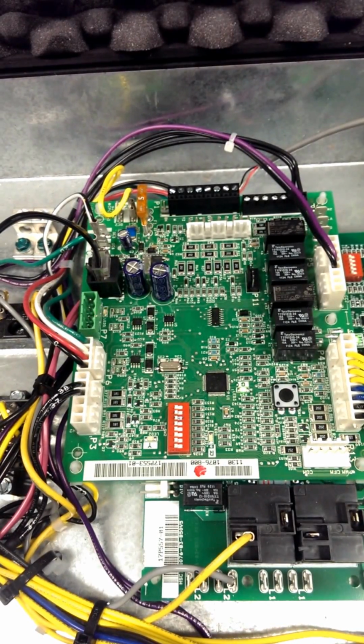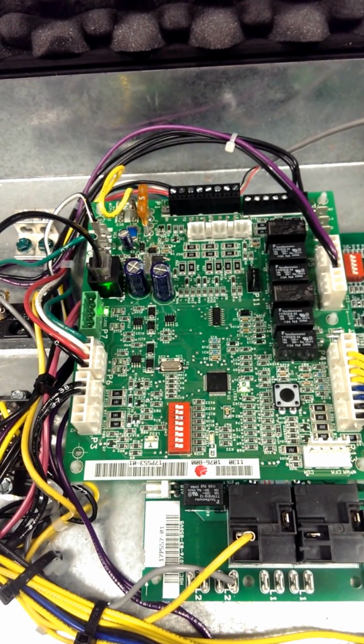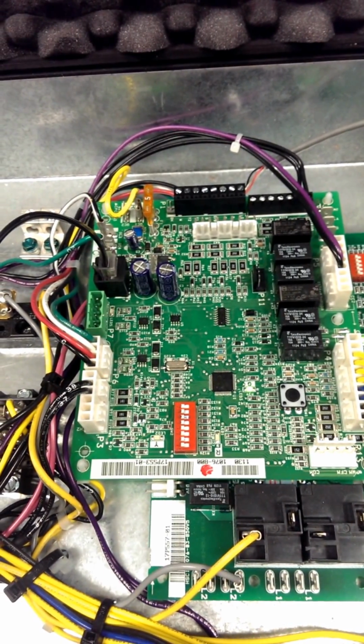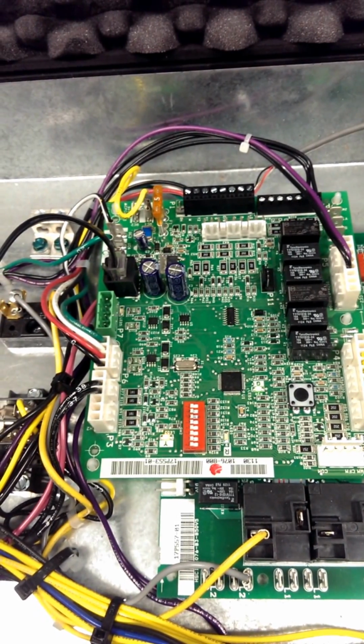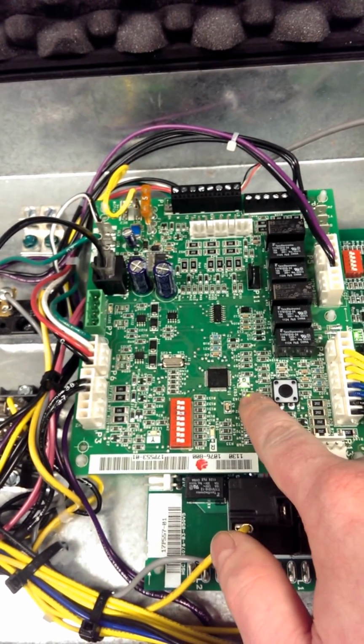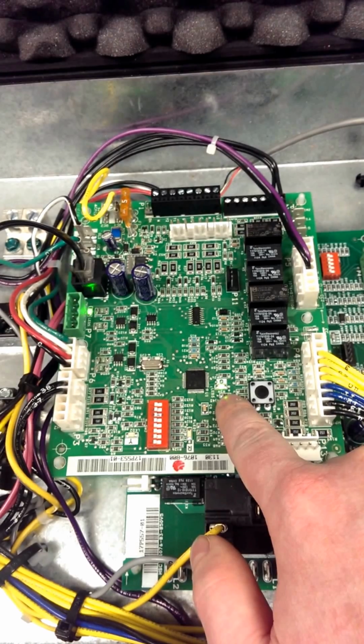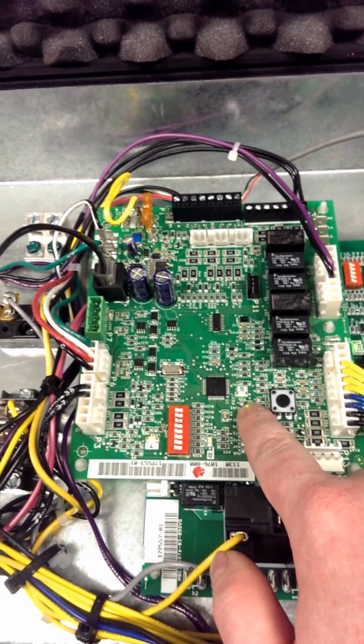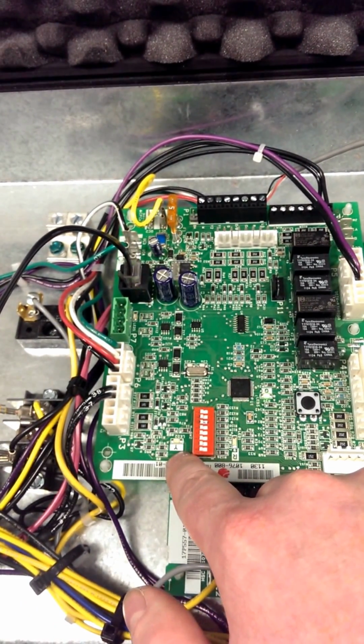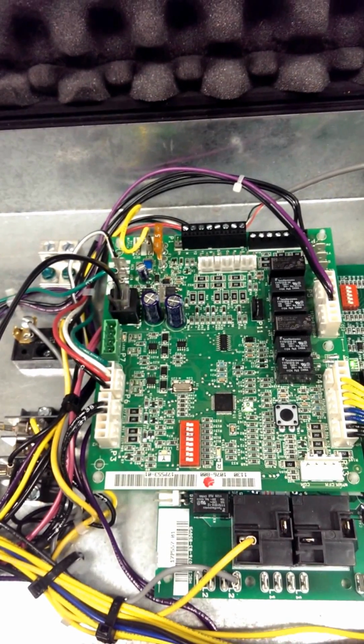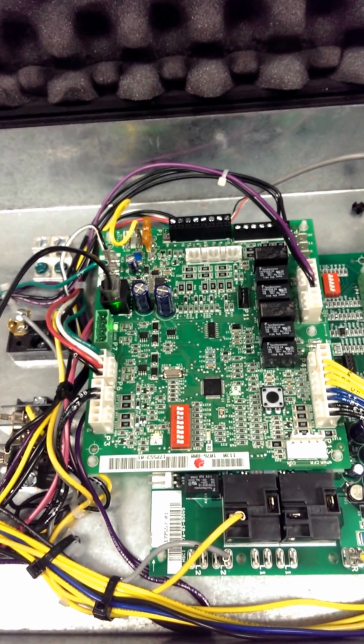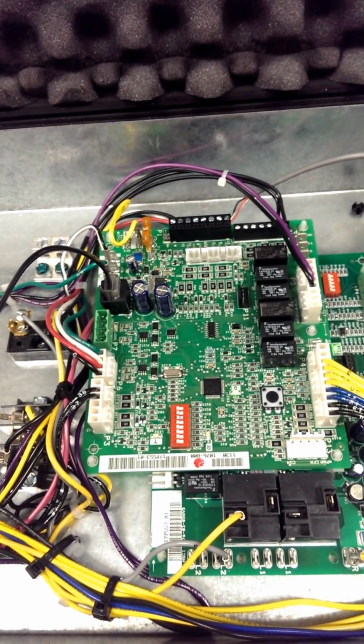In this video, we're going to show you how to manually set up the ECM speed settings on the Aurora board. Again, if you look at the board, we've got a few different flashing lights. In this case, we have a steady green light on the board that just tells us the status of the microprocessor. Right over here next to the dip switches, we have a flashing yellow light. That flashing yellow light is actually telling us what speed the fan is set up for right now.